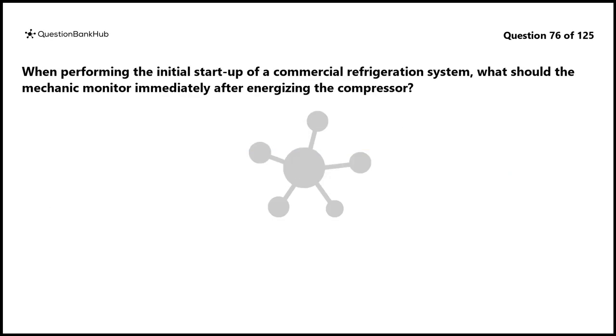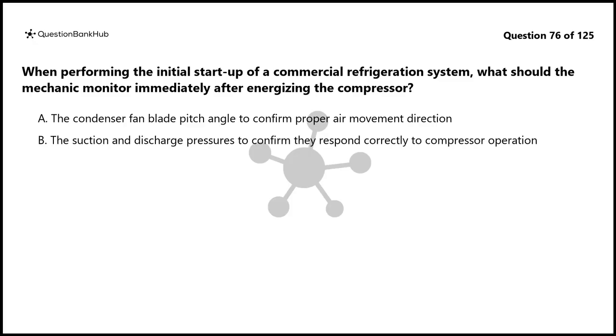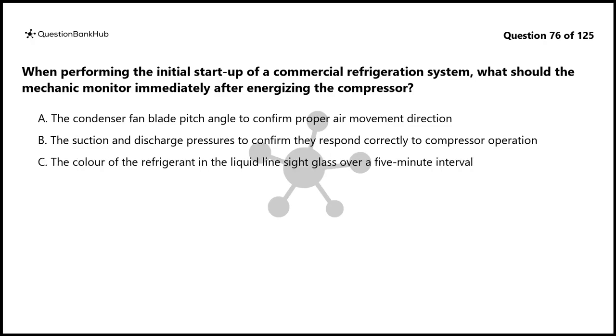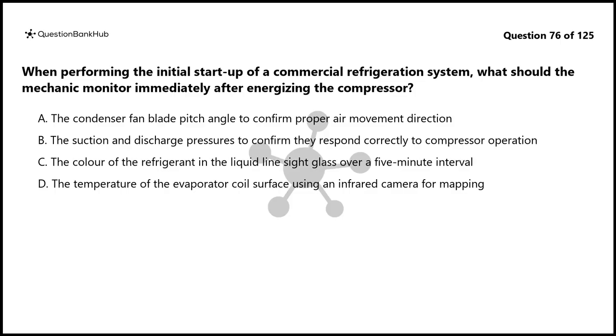Question 76. When performing the initial startup of a commercial refrigeration system, what should the mechanic monitor immediately after energizing the compressor? A. The condenser fan blade pitch angle to confirm proper air movement direction. B. The suction and discharge pressures to confirm they respond correctly to compressor operation. C. The color of the refrigerant in the liquid line sight glass over a 5-minute interval. D. The temperature of the evaporator coil surface using an infrared camera for mapping.